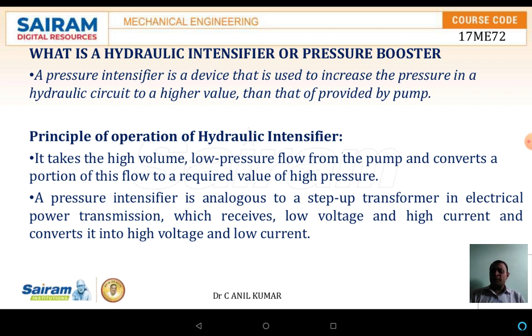The principle of operation of a hydraulic intensifier is to take a high volume, low pressure flow from the pump and convert the portion required to high pressure. A pressure intensifier is analogous to a transformer used in electrical power transmission, where low voltage at high current is converted into high voltage at low current.